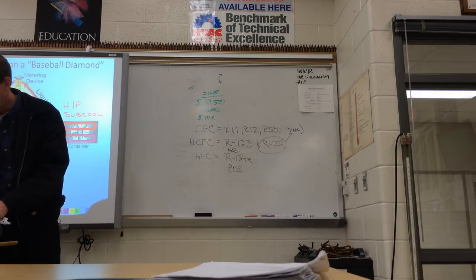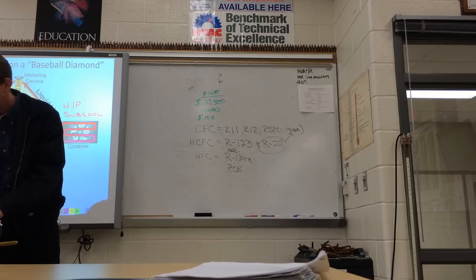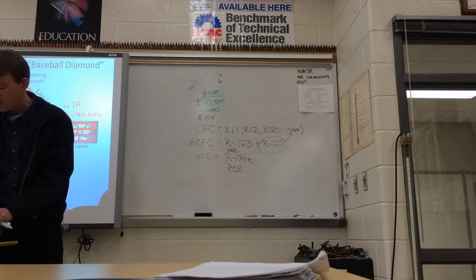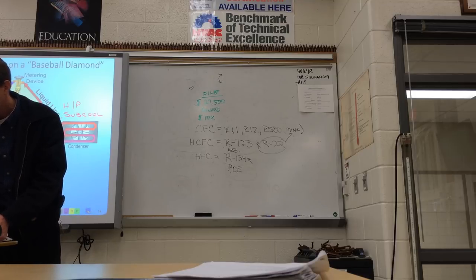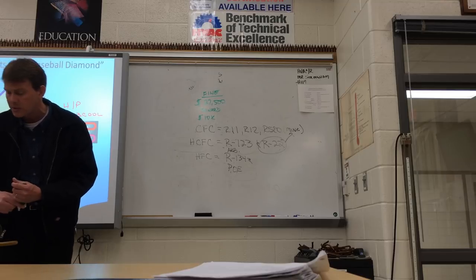Two types of recovery equipment, you've got system dependent. And that's one way of doing it where you're just relying on the system's pressure or the compressor of the unit if it's running. And then self-contained. Self-contained is we've got our own recovery machine that's going to do it for us. It's going to have its own compressor to suck the refrigerant out.